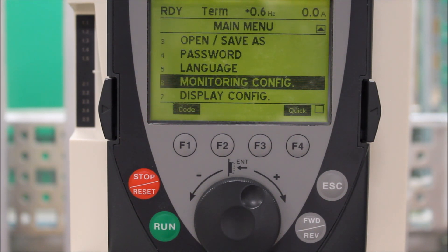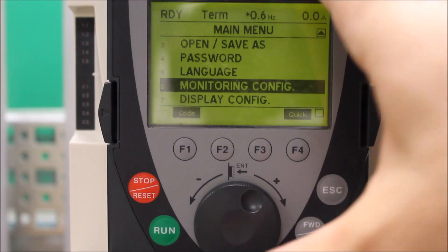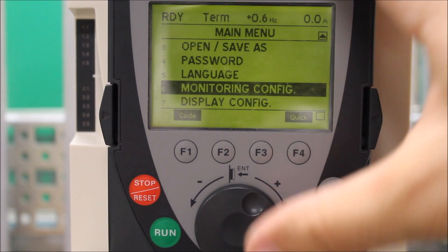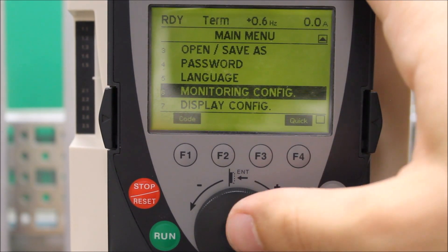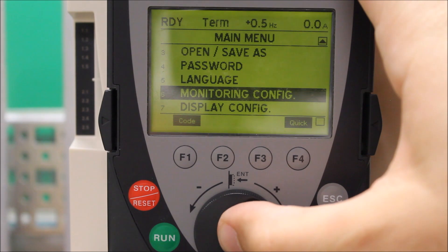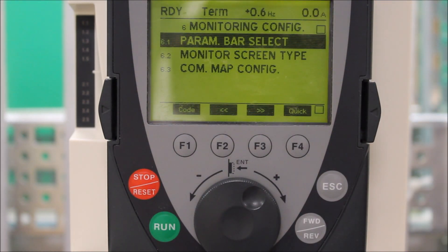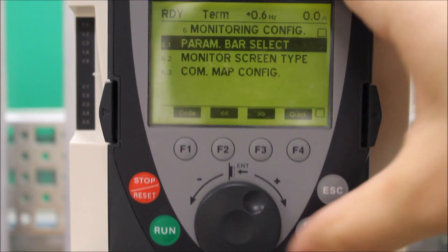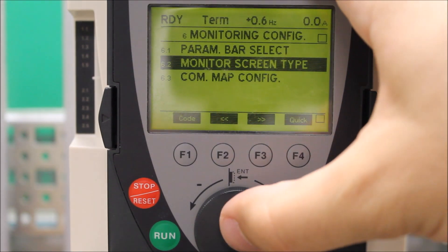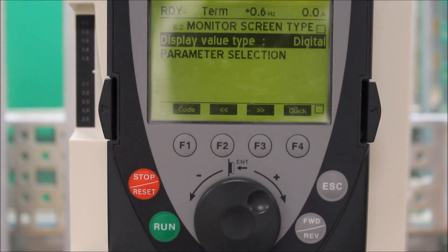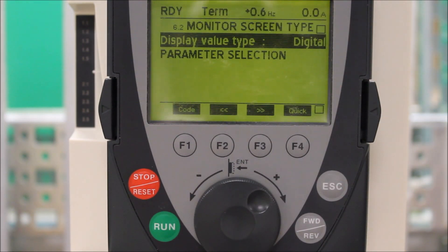The first thing you want to do here is under your main menu, find the menu called Monitor Configuration, menu 6. Enter. Then go down to your monitor screen type. The display value type from the default setting is digital.